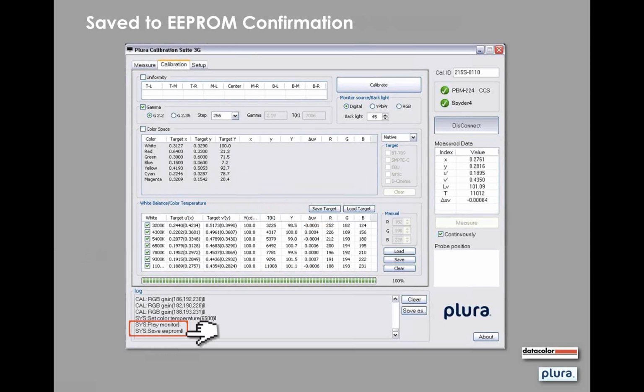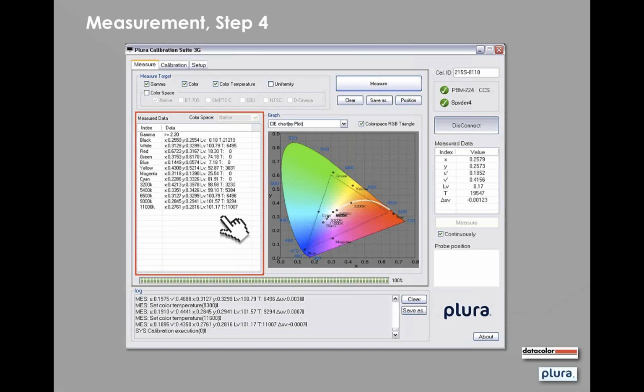Let's see. Right now we're on a calibration screen. But on the measurement tab, if you could go to that, David. Sure. One second. Okay. Yes, right here. As you see underneath the measure button towards the top, there's a save as, and that will save all the measured data that it measured. What's basically in that red square is what it'll save, in a notepad type of file that you could save on your computer just for future reference, if you wanted to come back to it in 6 months and see what it was actually measured as. And again, down at the bottom, the log for the measuring of the measurements can be saved also.